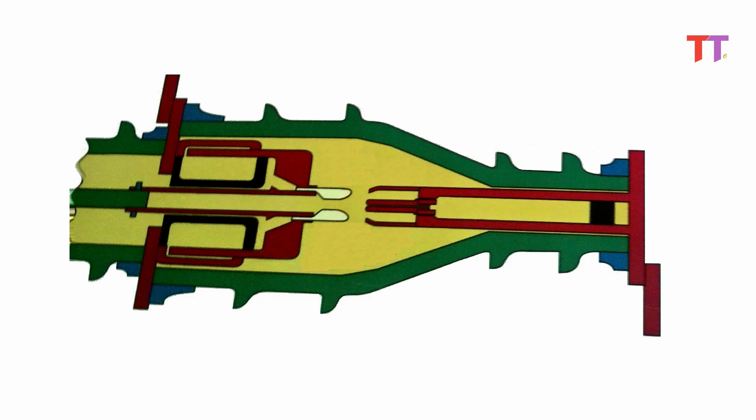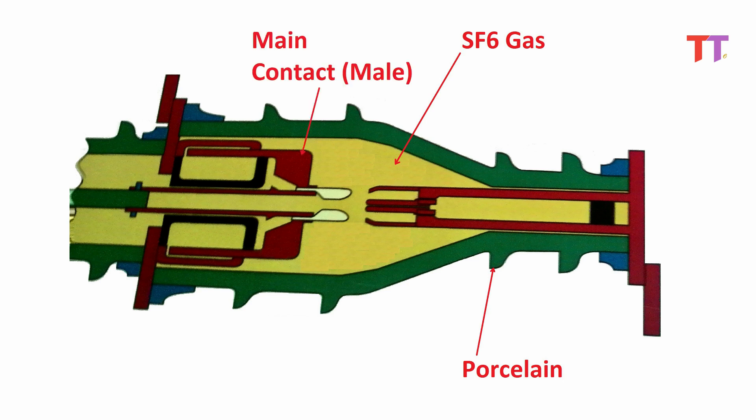Here in the diagram we can see longitudinal section of interrupter. This is airtight chamber filled with SF6 gas inside porcelain housing. We can see two main contacts. This one is male contact which is moving and this other one is female contact which is fixed.